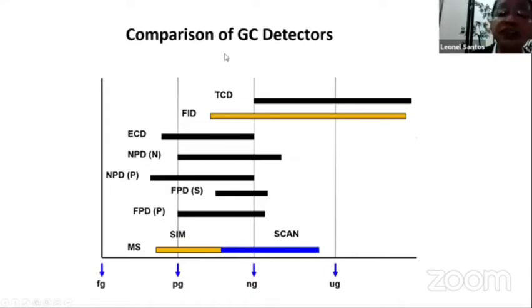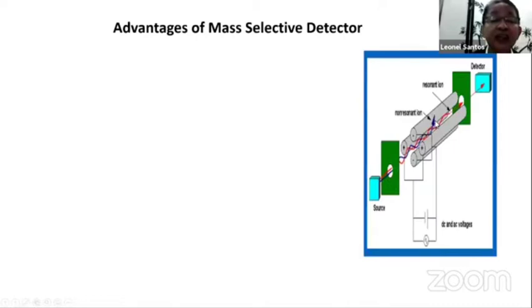In terms of the GC detector that you are using, the one typically used for residual solvents, as described in General Chapter 467, would be the FID, flame ionization detector. Shown here, it has a wider range, but a good one to use would be a mass selective detector. And I believe the Central Instrumentation Facility has this detector also, the mass selective detector.